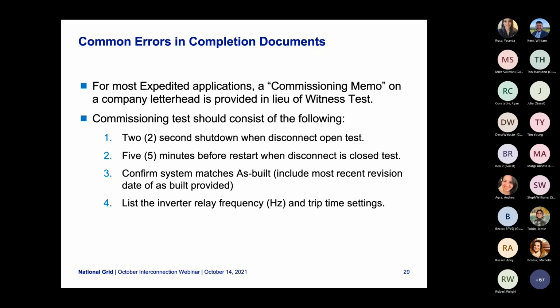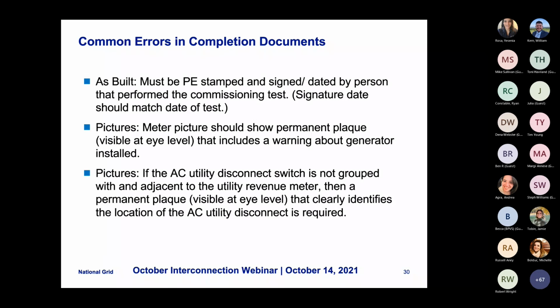So we want to have an as-built with the most recent revision with the date listed on that, agreeing with the commissioning memo and the as-built. So same signer, same date. List the inverter relay frequency and trip time settings. So insert that table as well on the commissioning memo. The as-built must be PE stamped and signed and dated by the person that performed the commissioning test. So they have to agree.